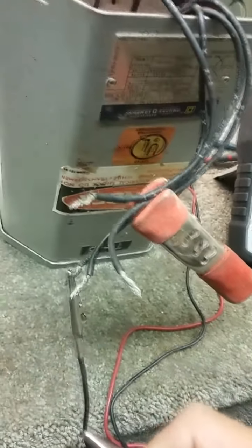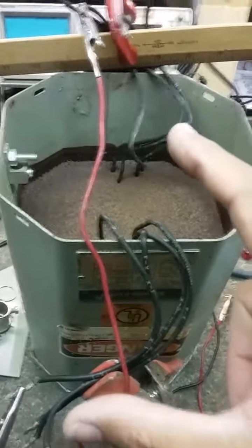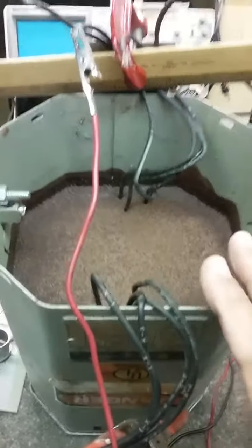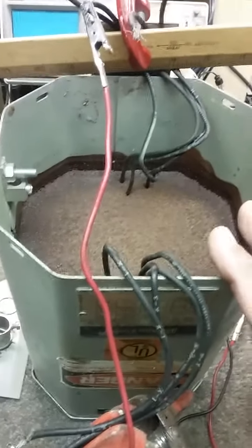Okay, so we're going to leave it on one of those coils. I'm on coil 2, and we'll check it to the primary. Nothing. If there's nothing here on the second coil of the primary, there can't be anything here because these are not shorted either. So now we'll put it on this one. It doesn't really matter, but just so you get an idea of what I'm doing, we'll move this to the first coil on the secondary, and again, no reading. So there's no shorts between the two primary coils or the two secondary coils, or from either of the primary coils to the secondary coils. This is a good transformer. It has no issues as far as short circuits are concerned.